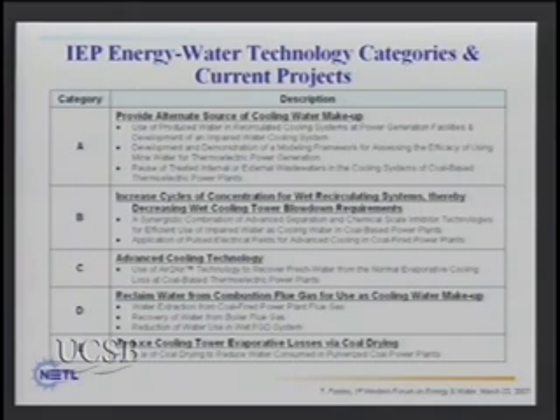One of the areas that has a lot of promise, and it's come up here in California, is using impaired waters in lieu of fresh water in a cooling cycle, whether that's industrial wastewater or produced water from oil and gas extraction. And in the east we've looked at using underground coal mine water in lieu of fresh water. Looking to increase the cycles of concentration around a cooling tower so you have less blowdown. You can run that water through more times before you have to blow down. That's an opportunity to reduce water loss.